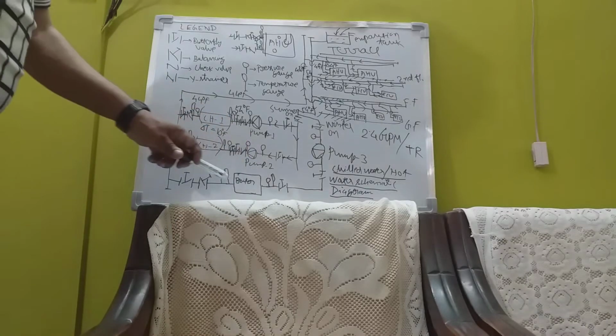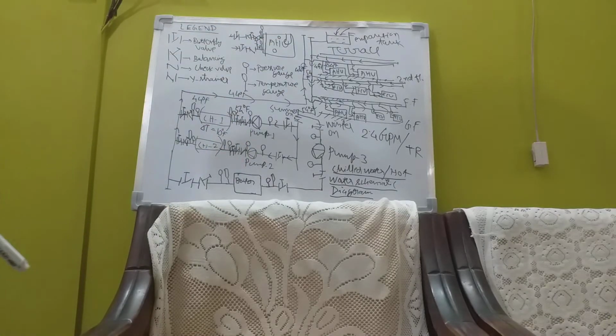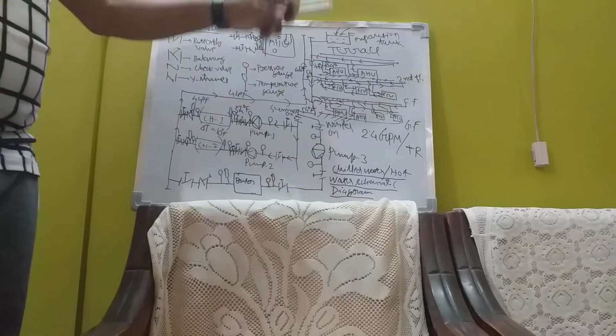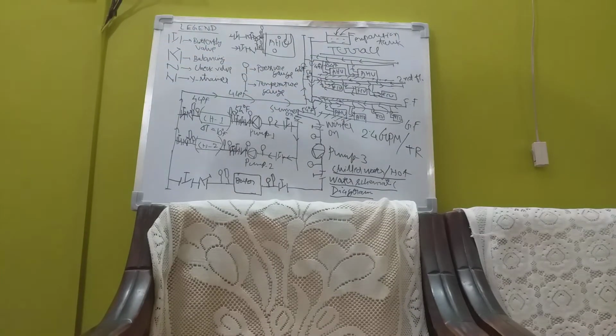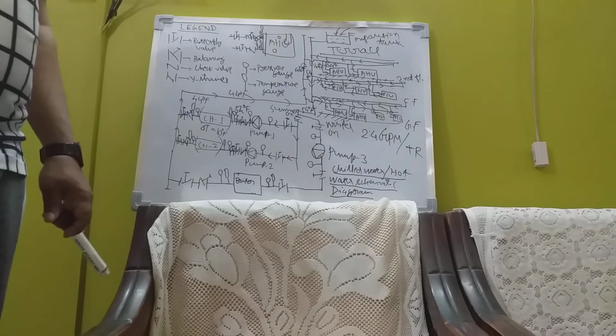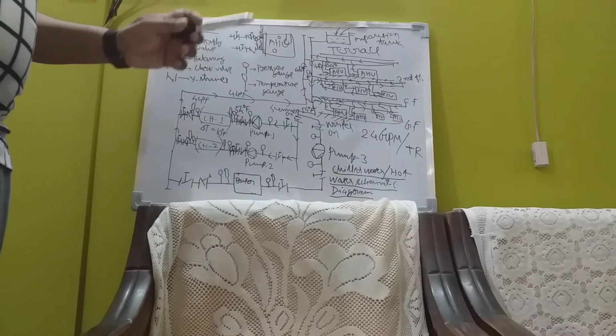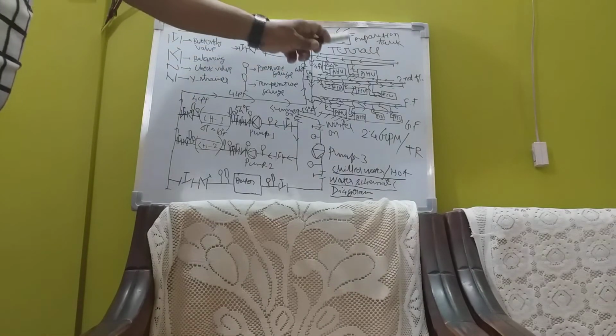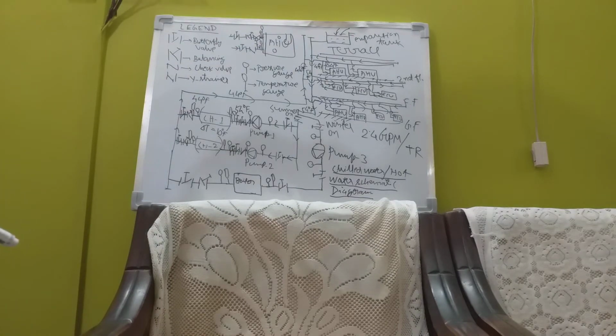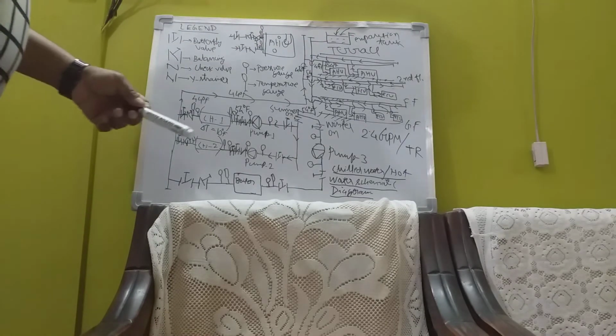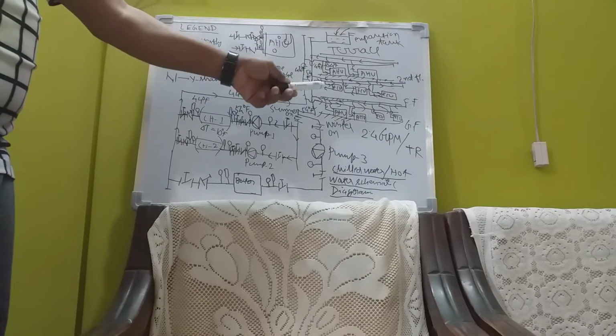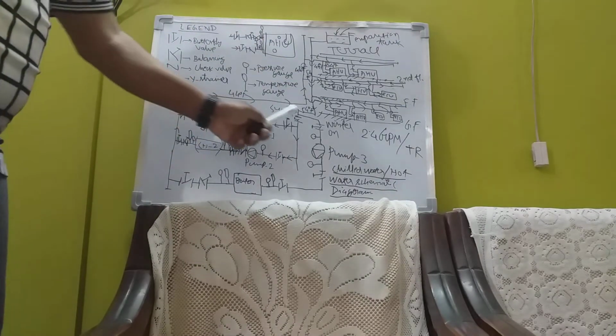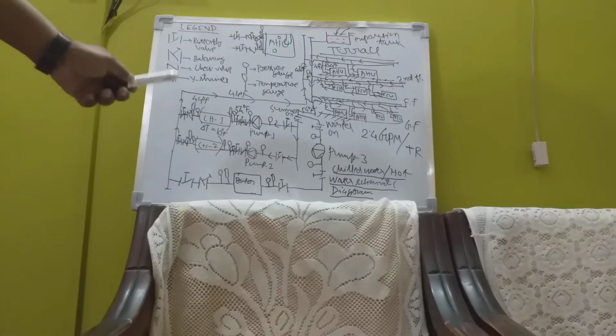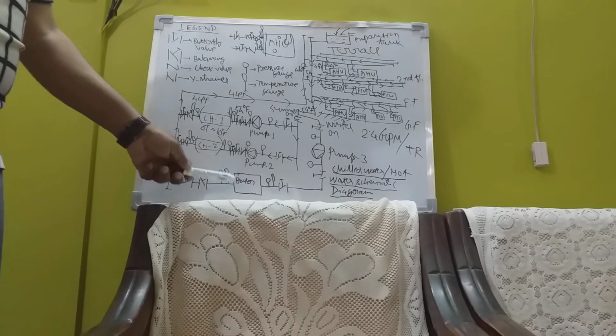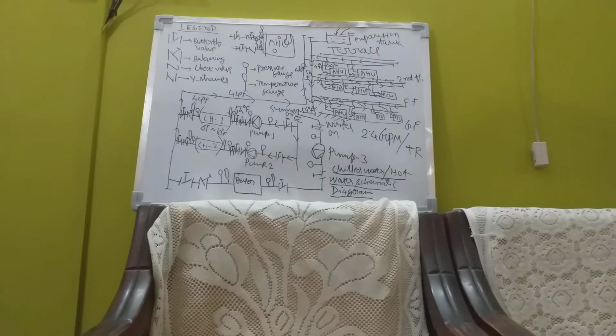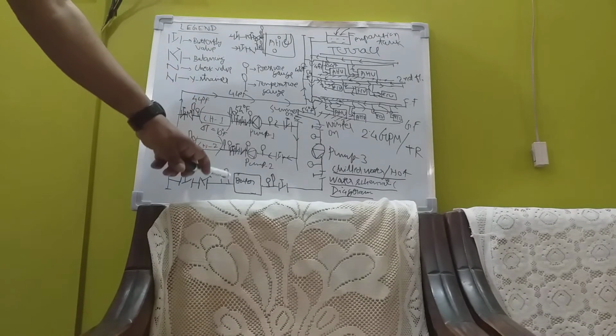This is what the boiler is doing in the hot water piping system. The same piping I am using for chilled water as well as hot water. Try to understand this whole phenomenon. This is very important. I am supplying both chilled water and hot water to the system. The same pipeline I am using for chilled water and hot water, with a change in the plant room. In the plant room, we are putting chilling machines and then a separate boiler. All are in parallel lines.